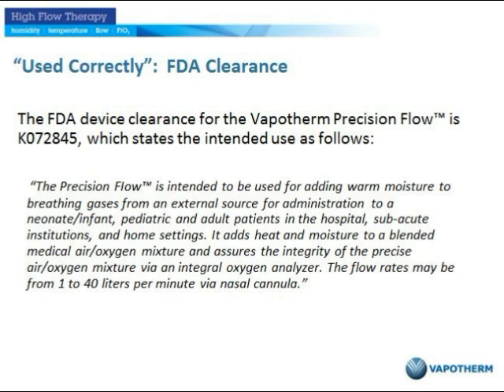Just to be clear, the FDA device clearance for the most current model of Vapotherm, the Vapotherm Precision Flow, is the FDA number that you see in front of you, which says verbatim, it's intended to be used for adding warm moisture to breathing gases from an external source for administration to a neonate, infant, pediatric, or adult patients in the hospital, subacute, and home settings. It adds heat and moisture to a blended medical air-oxygen mix and assures the integrity of the precise air-oxygen mixture via an integral oxygen analyzer. The flow rates may be from 1 to 40 liters per minute via nasal cannula.